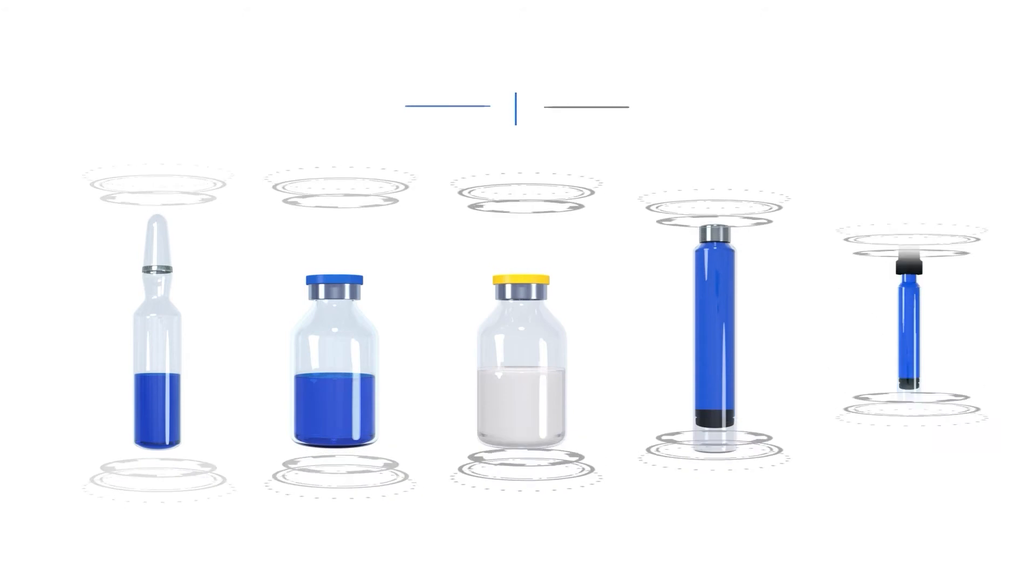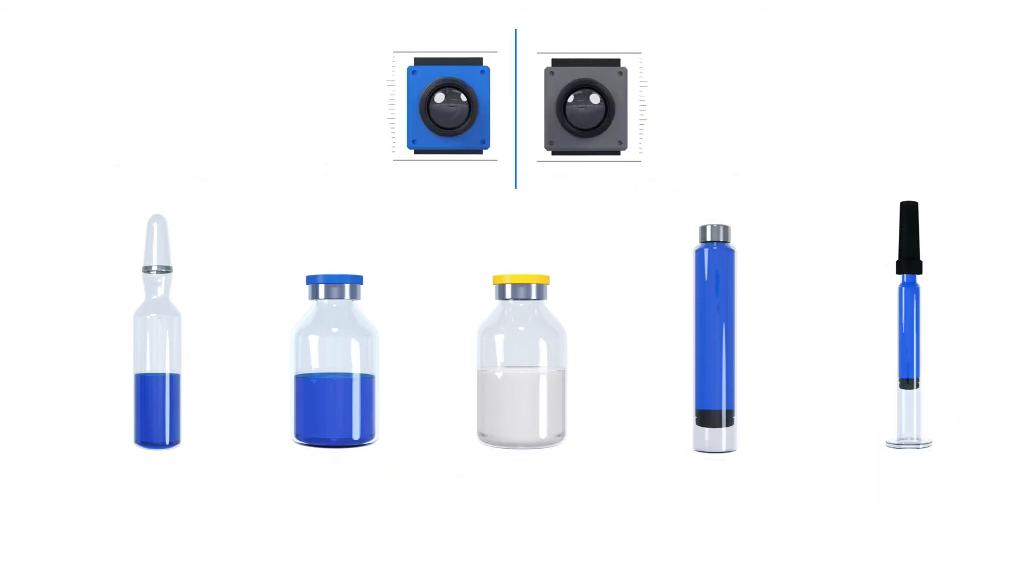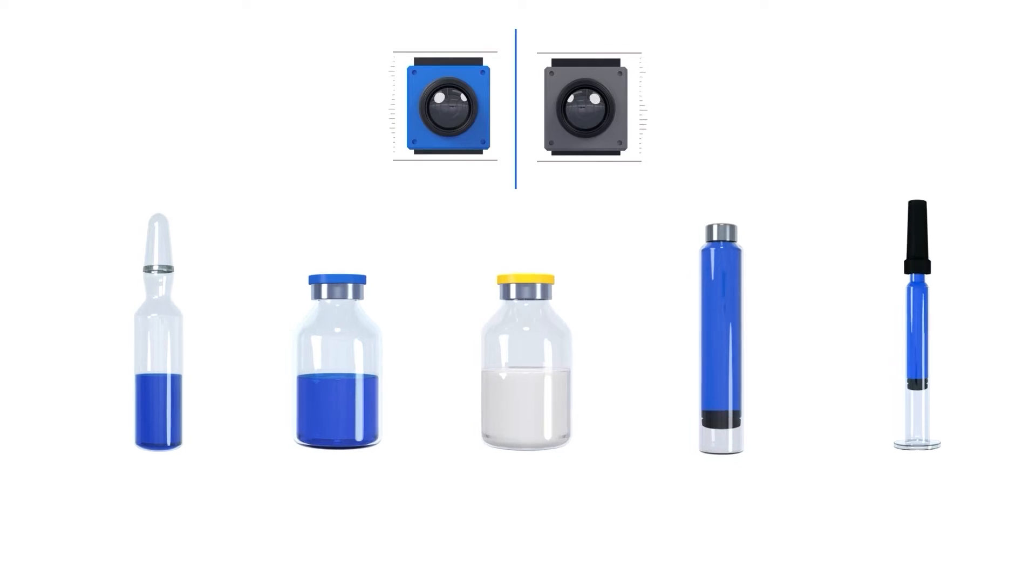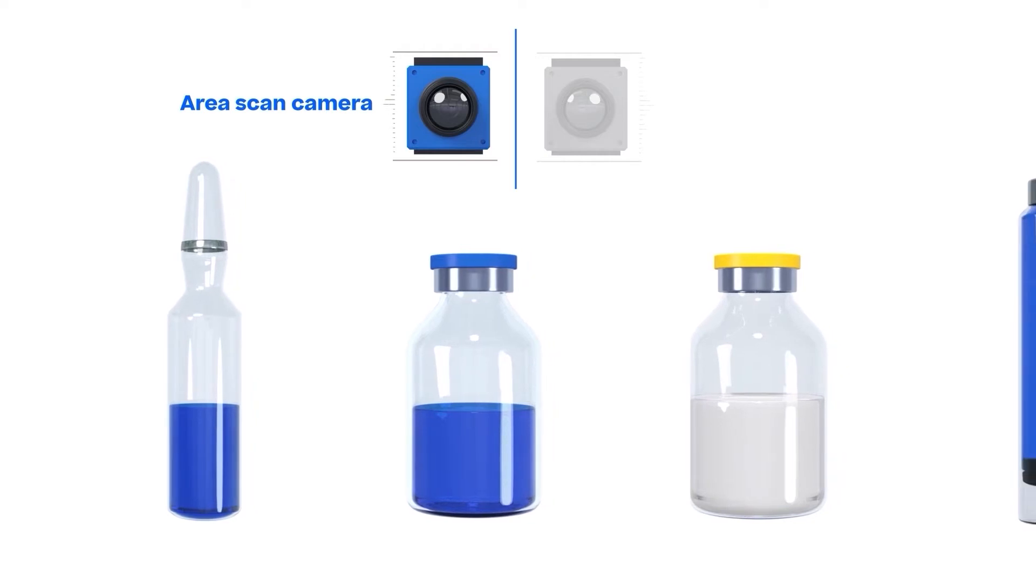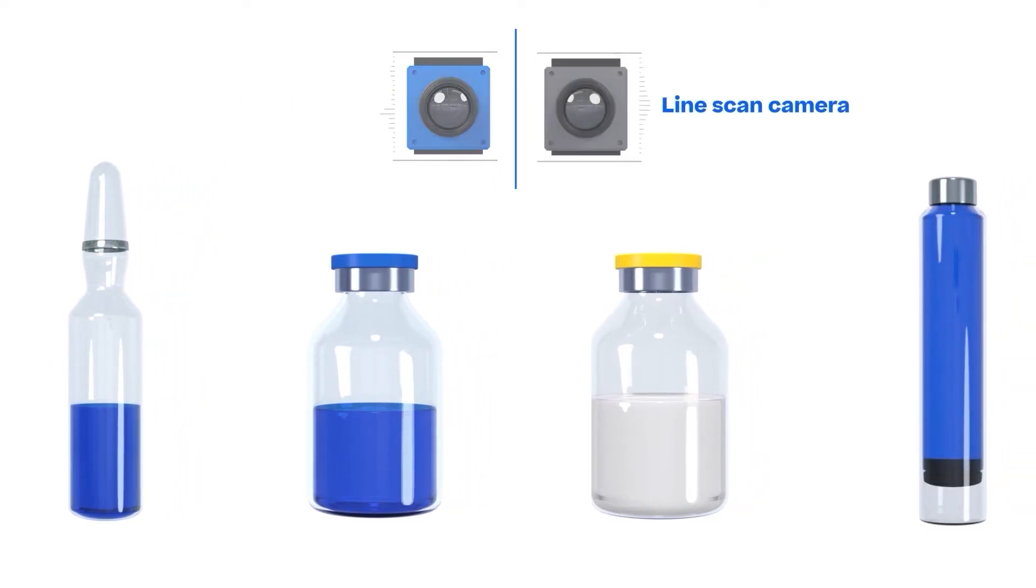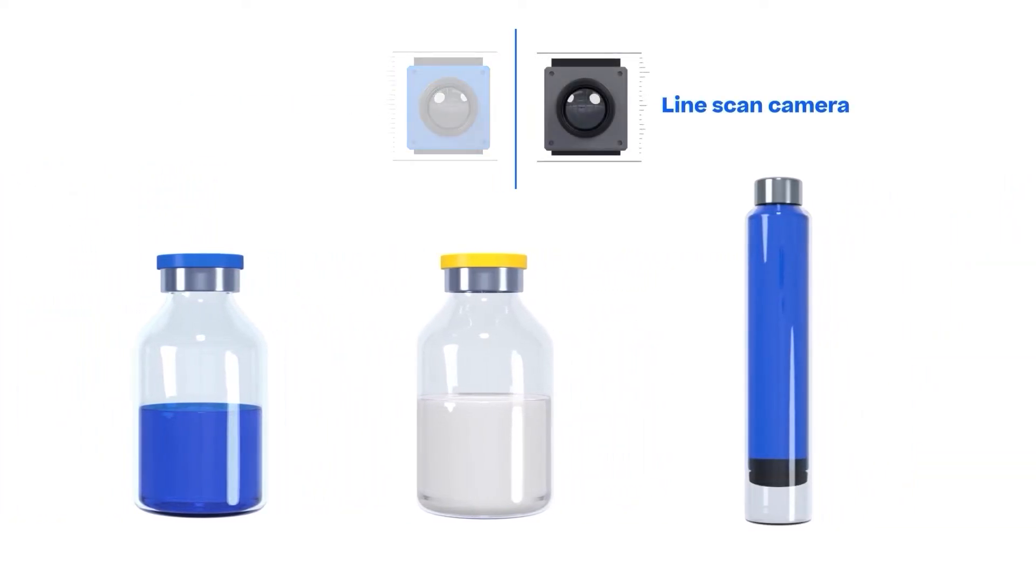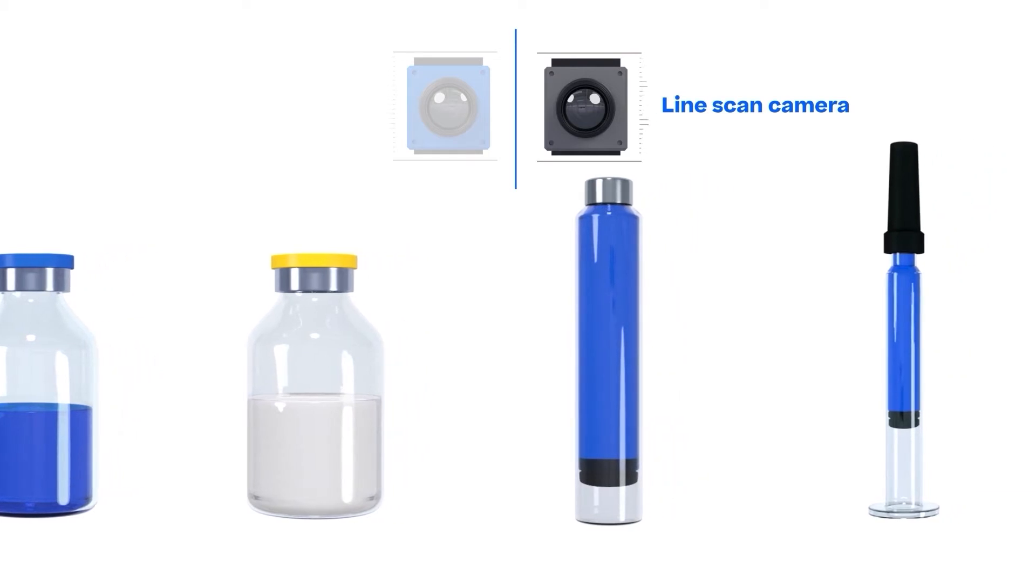Cameras are used for the vast majority of criteria in the inspection of pharmaceutical products. In most cases we employ area scan cameras. If our evaluation of a specific product being inspected concludes that a line scan camera is more appropriate, that type of camera will be used for the inspection.